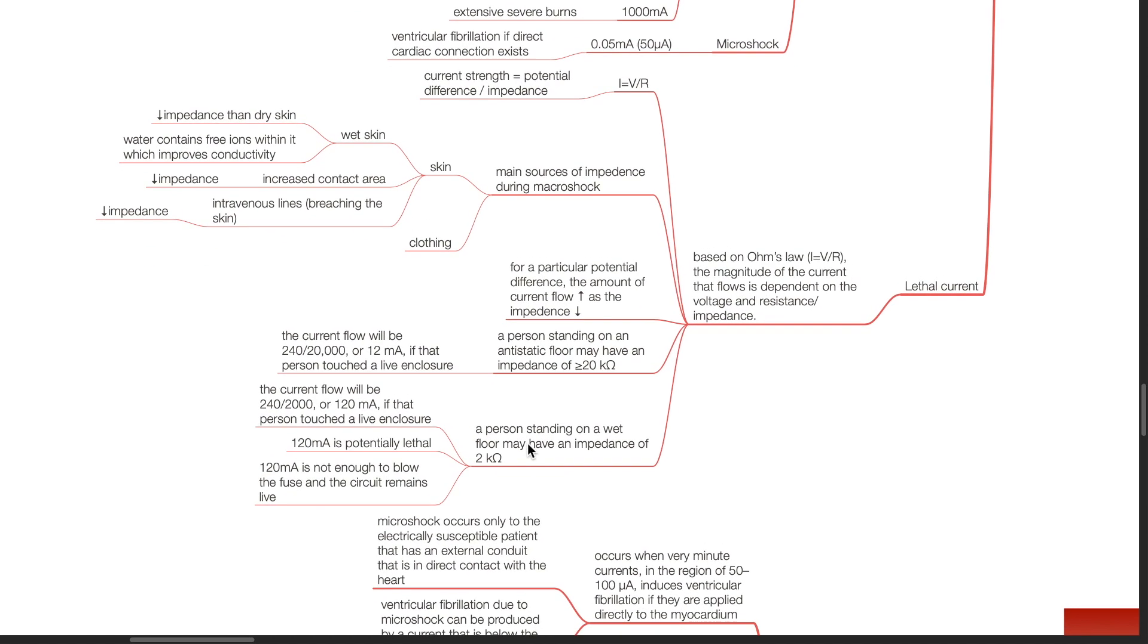However, a person standing on a wet floor may have an impedance of 2000 Ohms. The current flow will be 240 divided by 2000 or 120 mA if that person touched a live enclosure. 120 mA is potentially lethal. However, it is not enough to blow the fuse and the circuit remains live.